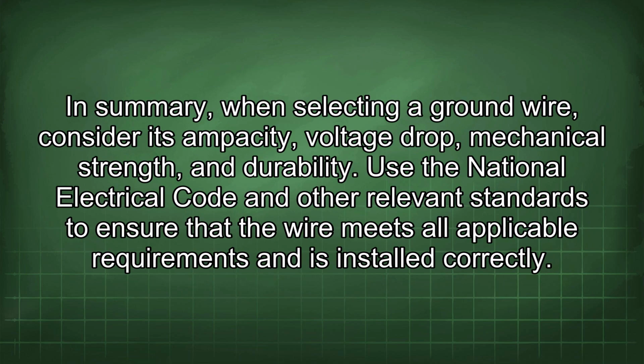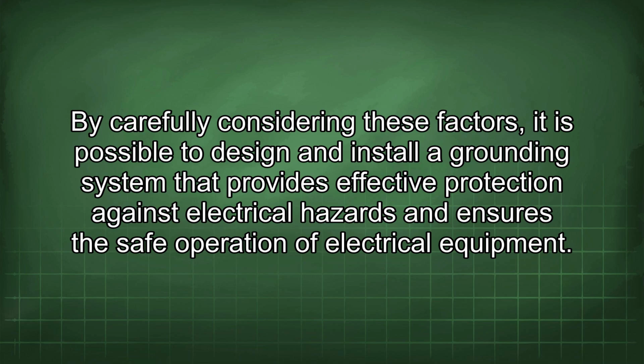In summary, when selecting a ground wire, consider its ampacity, voltage drop, mechanical strength, and durability. Use the National Electrical Code and other relevant standards to ensure that the wire meets all applicable requirements and is installed correctly. By carefully considering these factors, it is possible to design and install a grounding system that provides effective protection against electrical hazards and ensures the safe operation of electrical equipment.